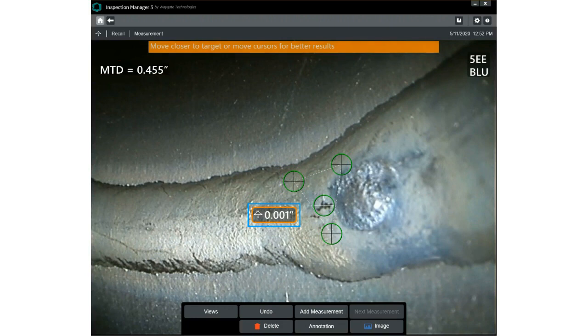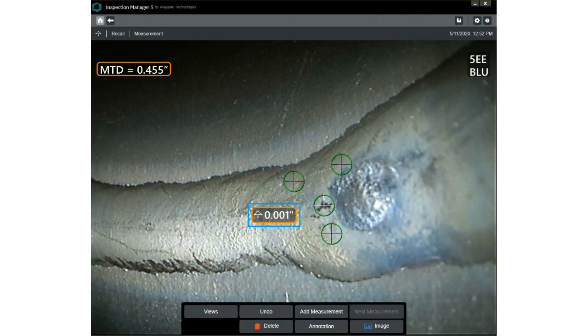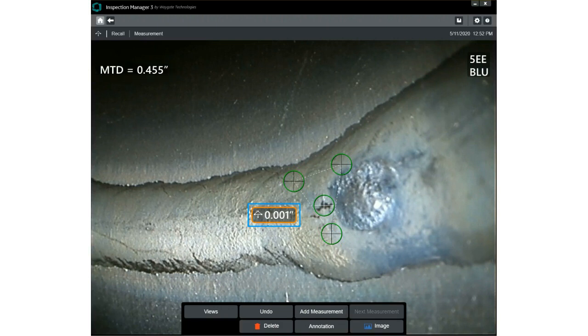The dynamic message says to move closer to target or move the cursors for better results. The cursors are where they need to be, so the only option is to get closer than 455 thousandths of an inch to this indication to get a valid measurement. Measuring from too far away means you cannot confirm whether there is any depth there.